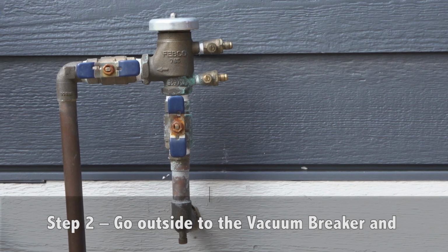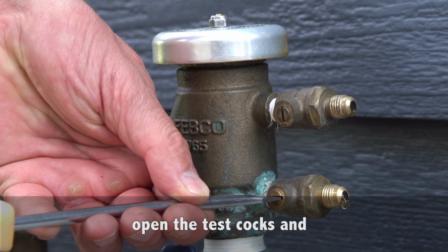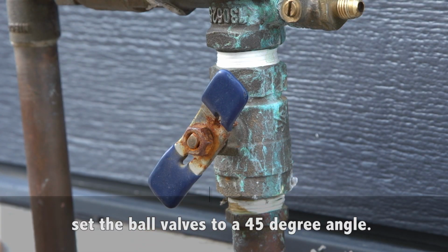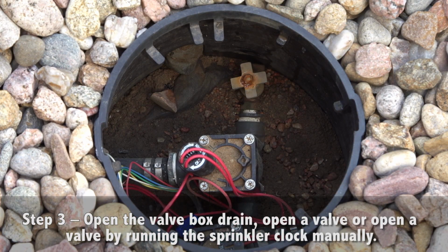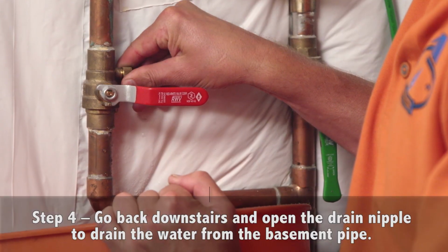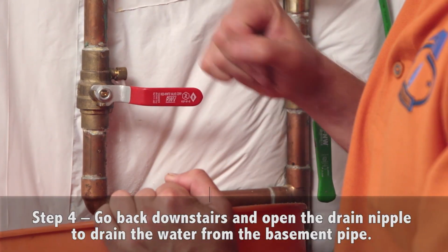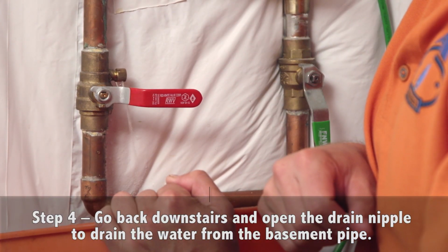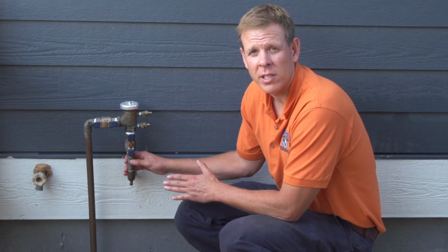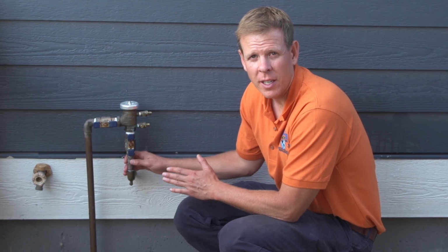Step 2, go outside to the vacuum breaker and open the test cocks and set the ball valves to a 45-degree angle. Step 3, open the valve box drain or open a valve. Step 4, go downstairs and open the drain nipple to drain the water from the basement pipe. So now we're going to head downstairs to do step 1 of the process.